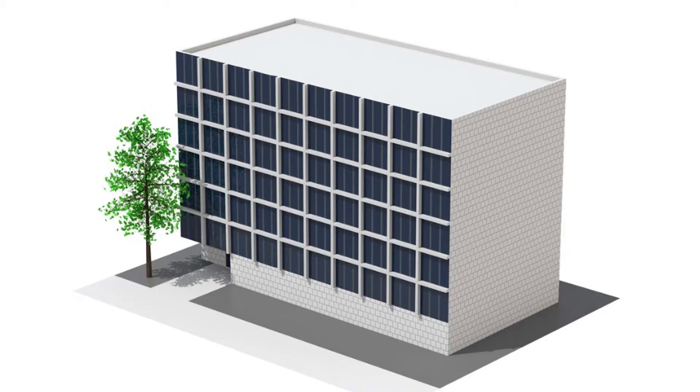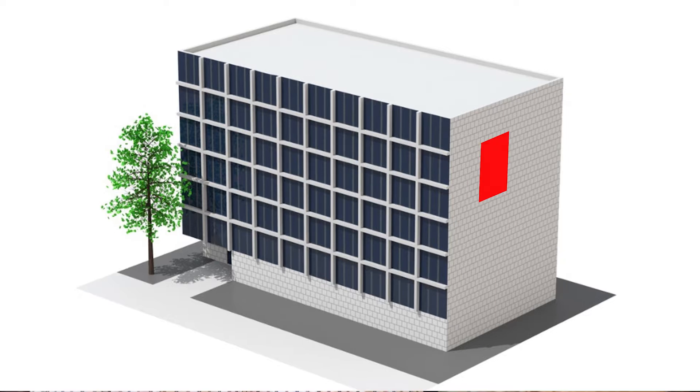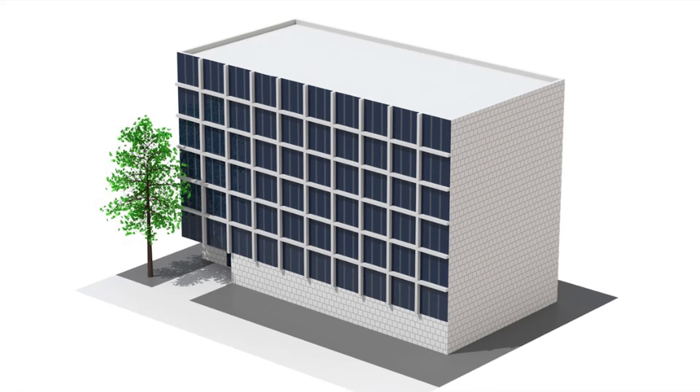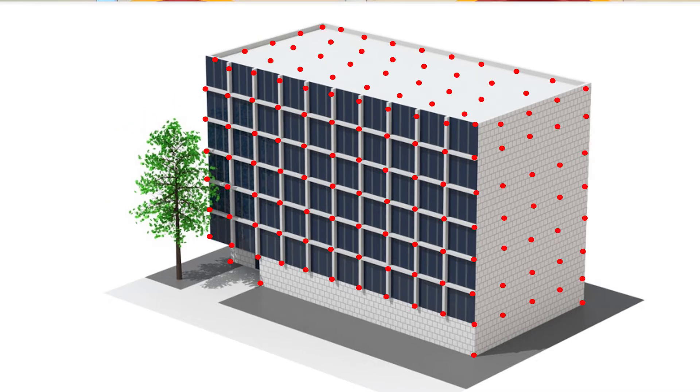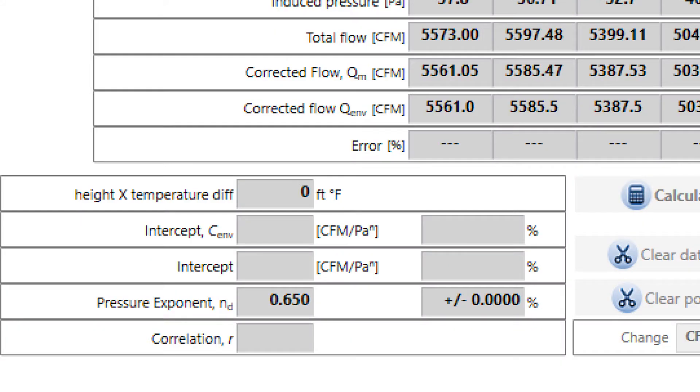One thing that number can tell you — it falls somewhere between 0.5 and 1.0. The closer it is to 0.5, the more of a wide open hole that you have. The closer it is to 1.0, the closer that building is going to have to a bunch of small holes. So that's a good way to tell how that building is leaking by looking at that number. You have to do a multi-point test in order to get that; otherwise it just assumes 0.65.